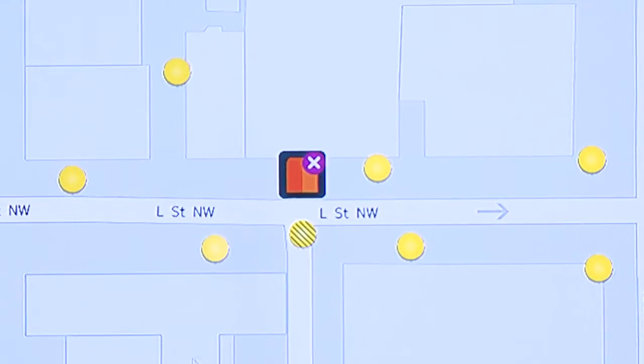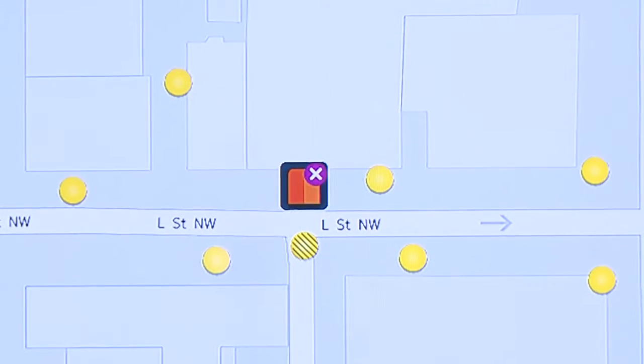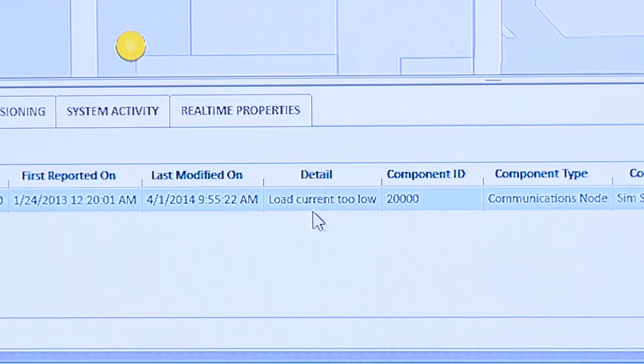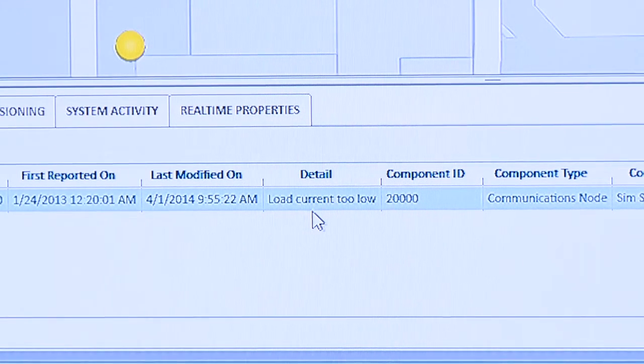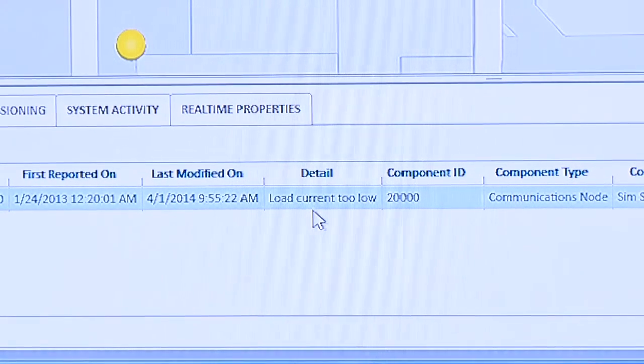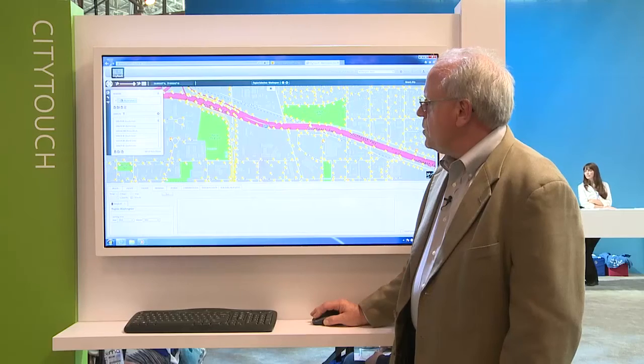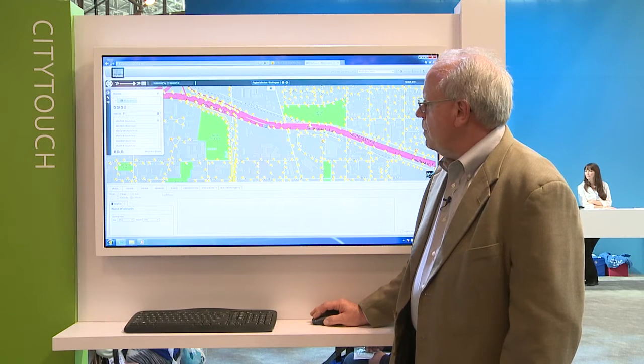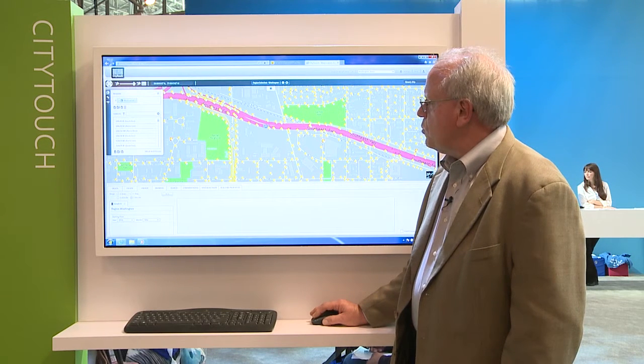In this case here, we have a fault on this streetlight indicated by the little red X. Down below, it provides a report saying that in this particular location the load current was too low based on the parameters that were established for this particular streetlight.